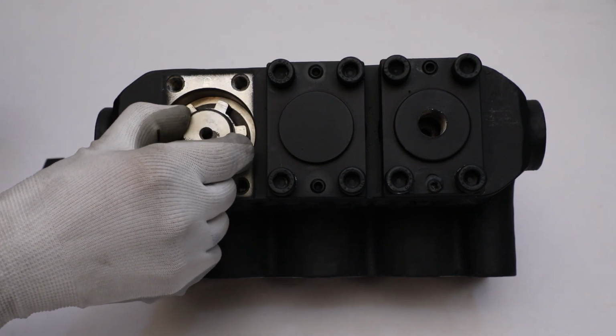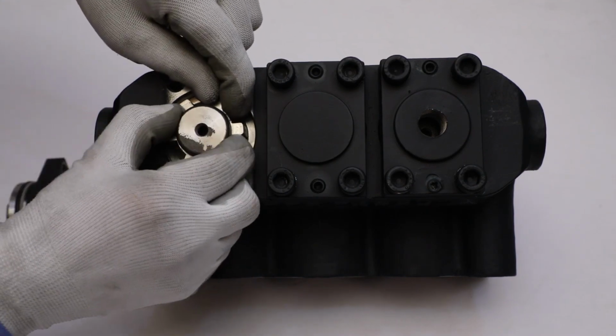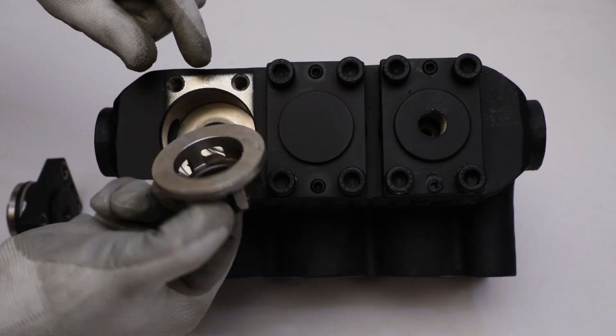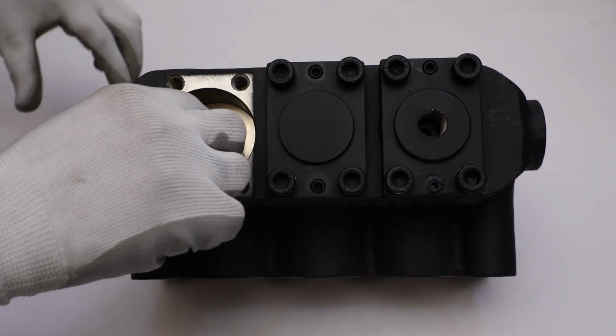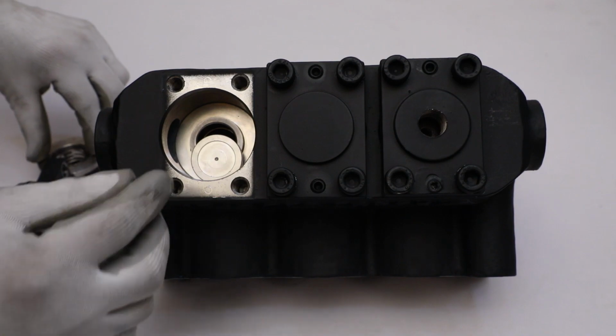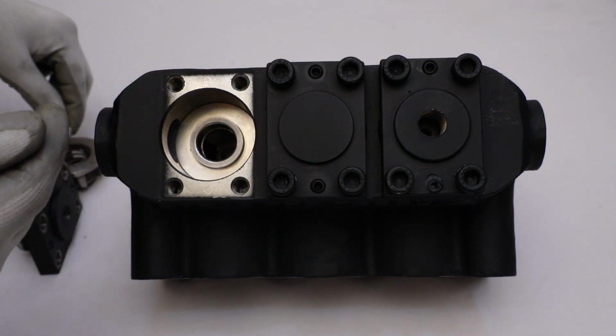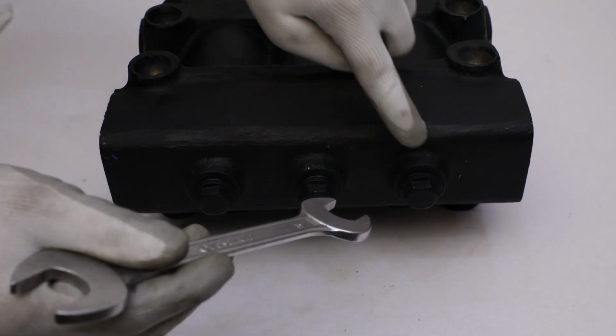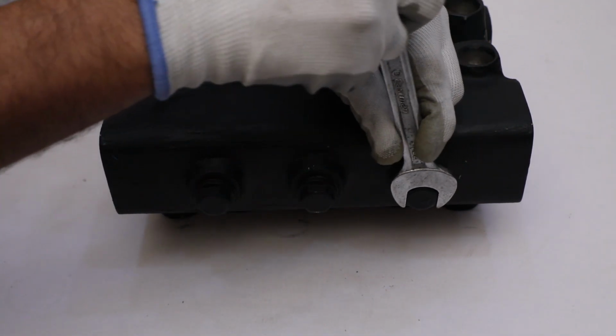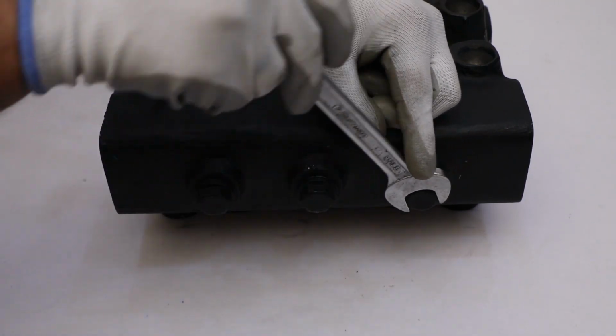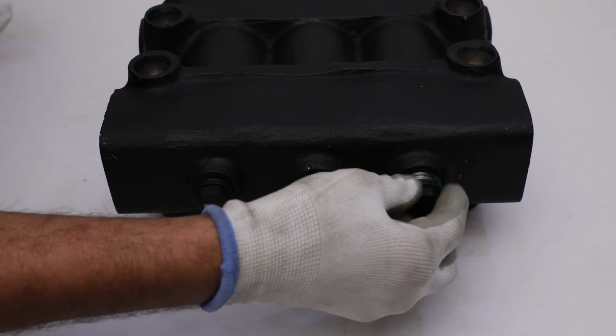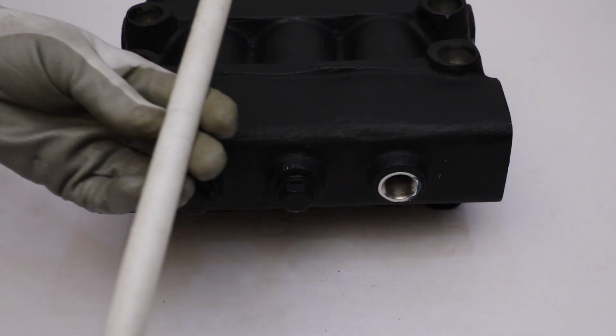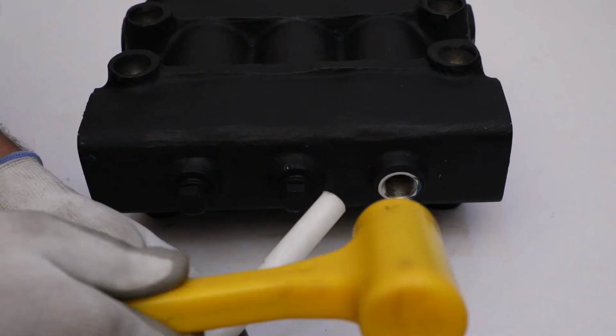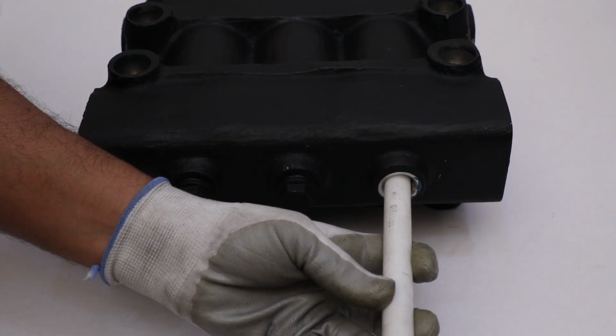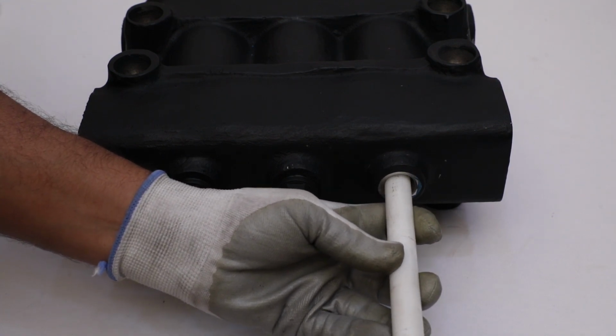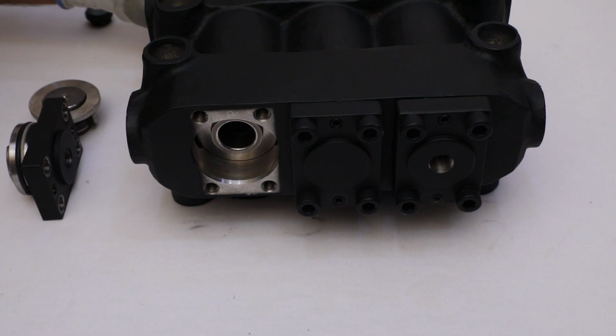Then take out discharge valve guide manually from the pump head. Take out helical spring, suction and discharge valve plate. Take spanner to unscrew the solid plug to eject the remaining elements of the valve assembly. After that, take a nylon rod and insert it into the pump head from a hole of solid plug. Using a rubber hammer, gently push the nylon rod to take out the remaining parts of a valve assembly.